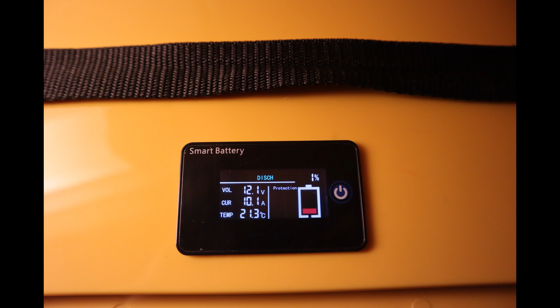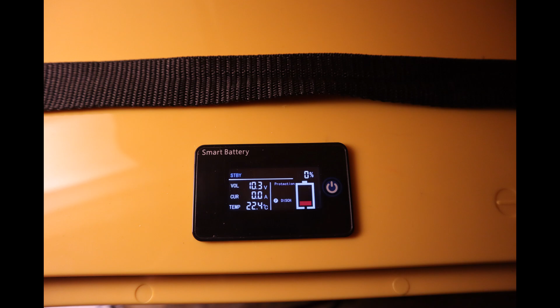At this point in the discharge test, the battery's internal meter is saying there's 1% capacity left. The voltage at the output is 12.1 volts, and it's still providing 10.1 amps of current. Once the battery has been fully discharged and the internal BMS has shut down the output, the meter reads 0% capacity. There's 10.3 volts internally, but 0 current flowing. This thing is now fully discharged.